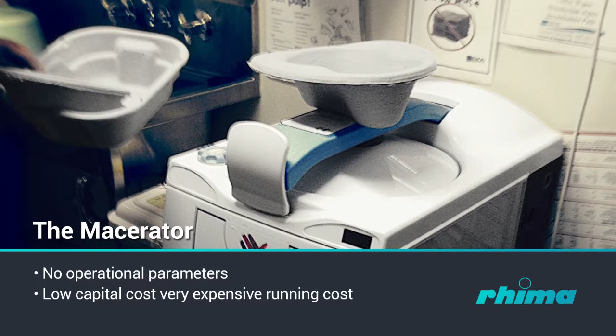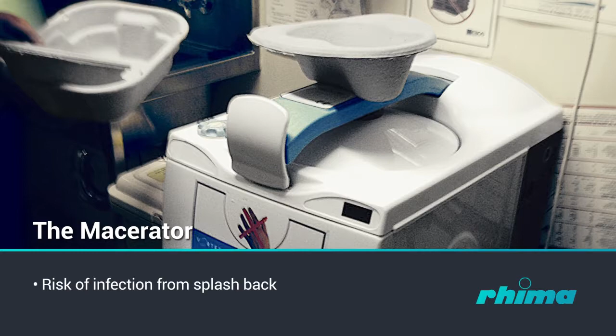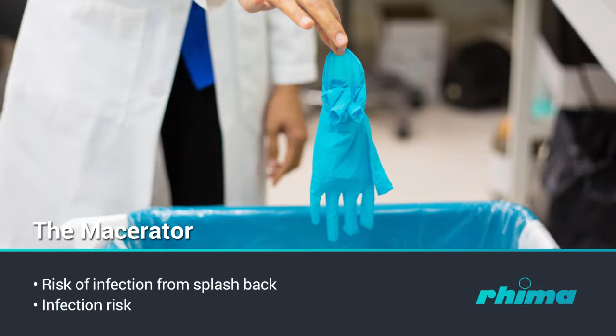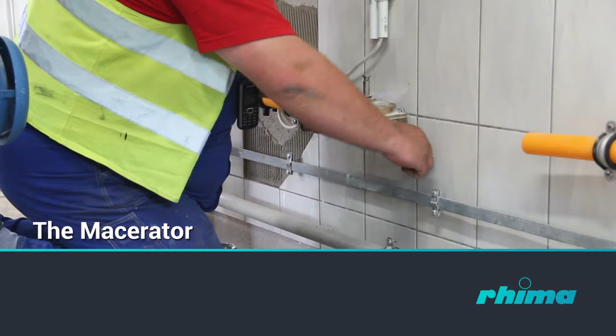Let's compare two major human waste disposal processing machines available today. The macerator, basically a glorified waste disposal unit that has a low capital cost but masks ongoing and expensive running costs. Nothing is flushed clean or disinfected. They are not complex, and the risk of infection comes mainly from the splashback produced when the machine is blocked, usually caused by solid objects such as gloves, diapers, etc., that have been put in them by mistake. The large amount of pulp waste produced can lead to blocked sanitary sewage disposal pipes and wastewater overflows.